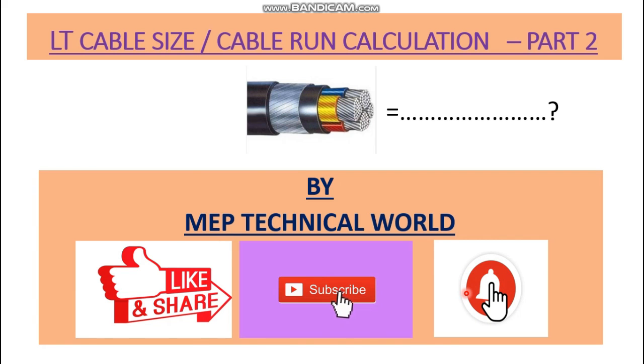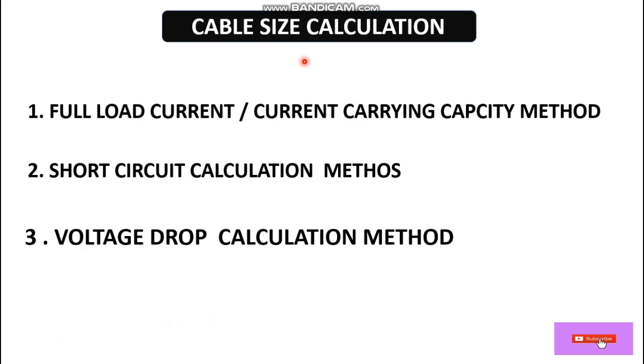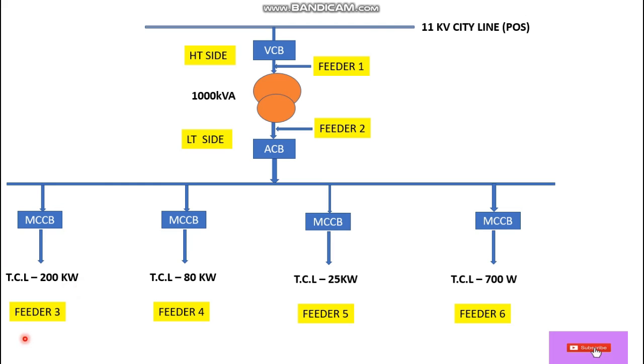Here we are calculating the cable as per the full load current carrying capacity method using the cable catalog. In further videos we will discuss two more methods. We also have to consider the short circuit and voltage drop while calculating the cable size. We'll first complete the current carrying capacity method, then we'll move to those two methods.